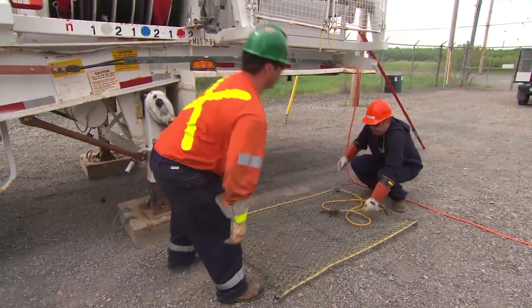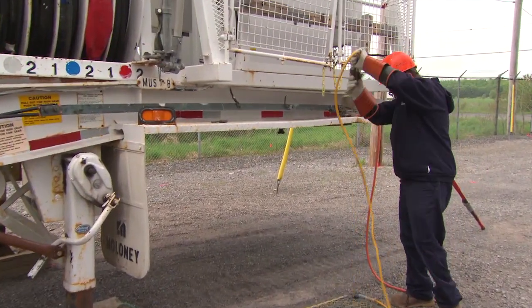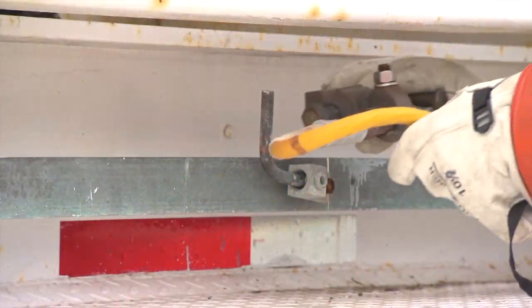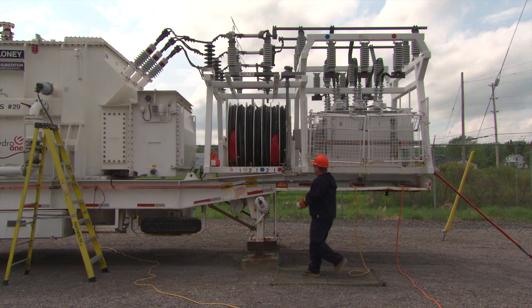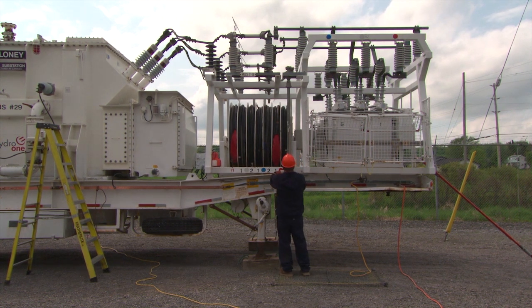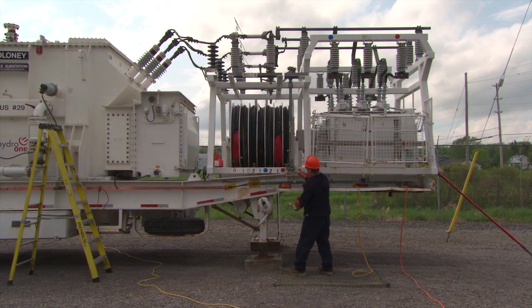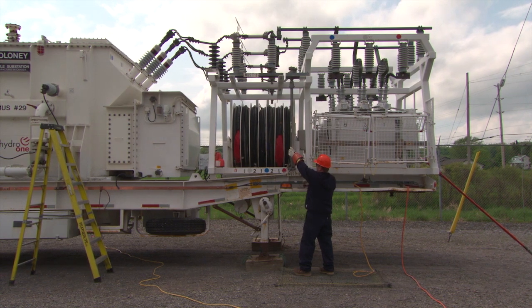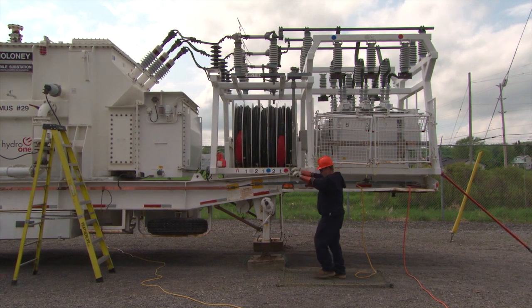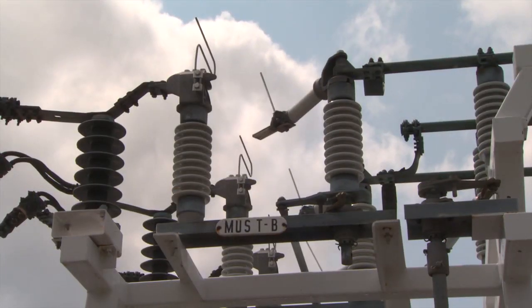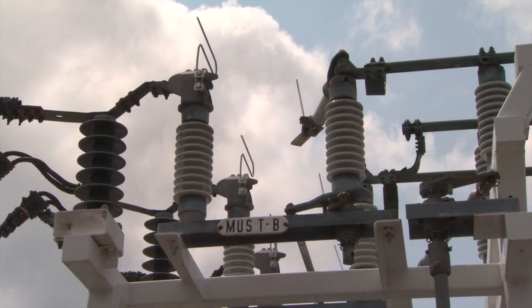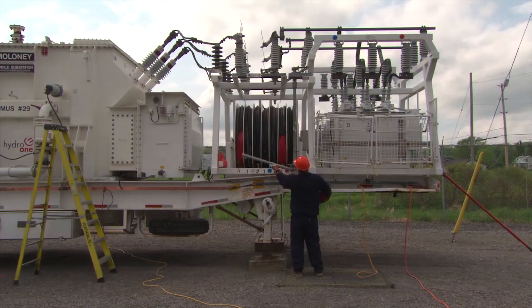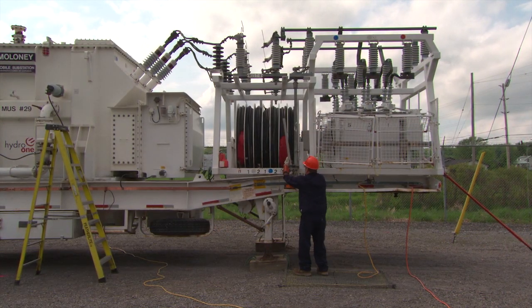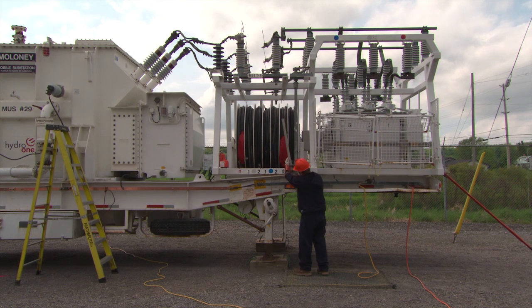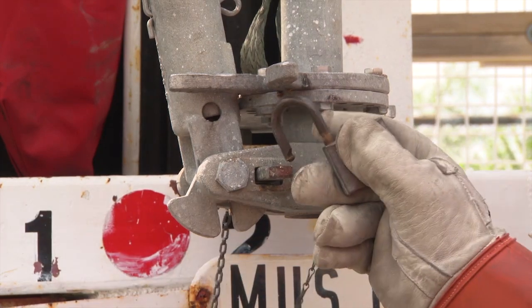Install the portable ground mat at the MUS T-B. While standing on the mat, test operate the switch. Check that the switch operates smoothly, the jaws line up, and the arcing horns touch before the main contacts are made. Clean and grease the contacts if required, and then lock the operating handle in the open position.